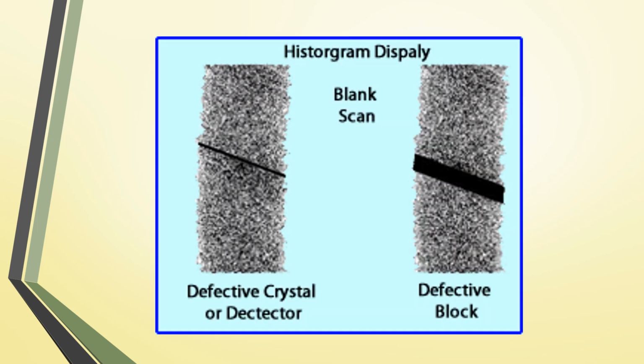This is an older picture. It's pretty grainy, but I wanted to use this to show you the comparison of a defective crystal in a PET scanner versus a detector block. Remember, the crystal is a much smaller component. A single PM tube is much smaller, whereas the detector block is several PM tubes grouped together. That typically has to do with a power failure or high voltage supply issue where the entire block becomes defective.